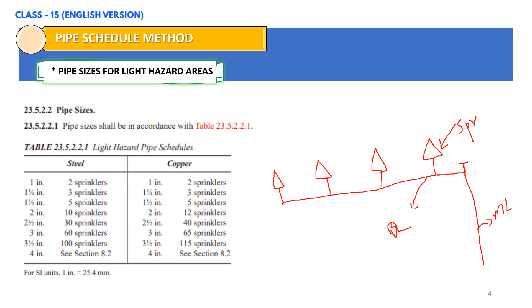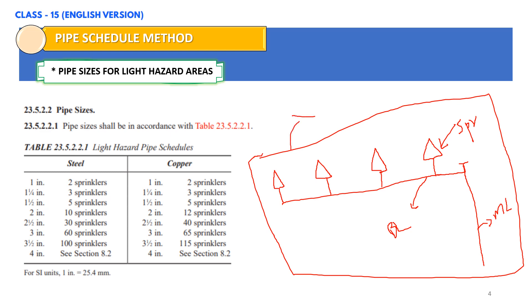Now, once we have the routing of the pipe and the distribution of the sprinklers based on NFPA 13, we can define the pipe sizes according to the pipe schedule method. For example, if the area we consider is an office, then it will come under light hazard occupancy. In light hazard occupancy, we need to start from the end. As you can see, for two sprinklers we can use one-inch pipe. So this will be one sprinkler — one-inch pipe can be used — and for the second sprinkler also, as per the pipe schedule for light hazard, we can go ahead with one-inch pipe.